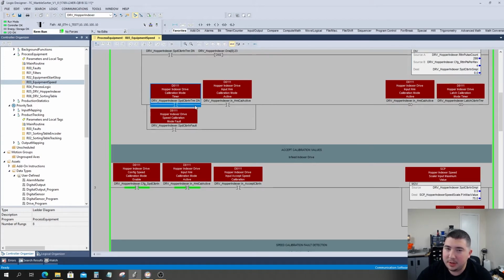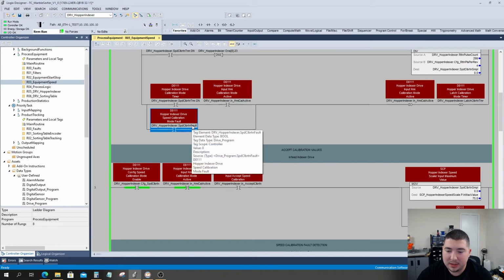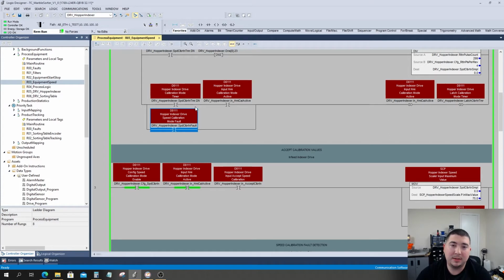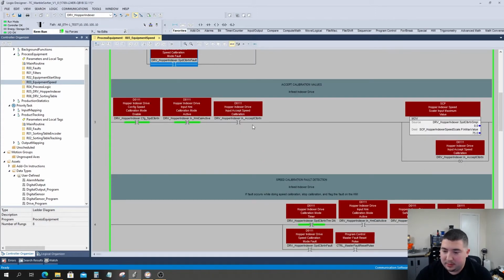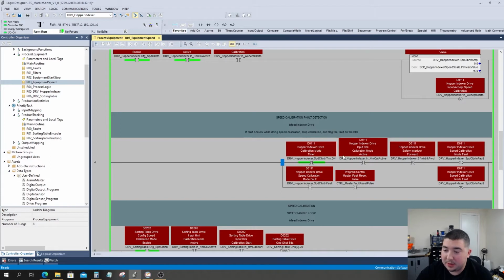In addition to turning off the command during normal functions, we also want to keep in mind that if something happens with the motor as far as a safety-based interference, we obviously aren't going to get a successful speed calibration. So in the event that something happens that forces the motor to fail, we will fault it. Now this is actually a speed calibration fault bit, but this is based on various interlocks that can indicate that the motor is in a failure during the calibration sequence. That way we won't continue to attempt the calibration mode until or during this fault status. So that's down here, our speed calibration fault detection.